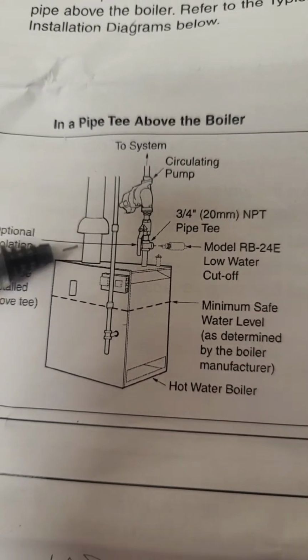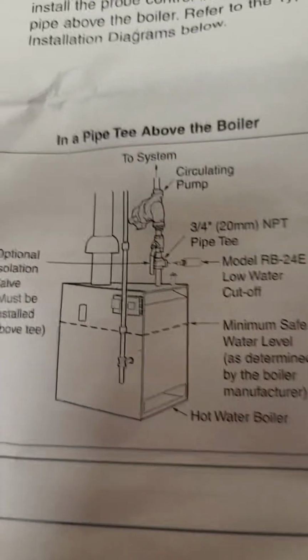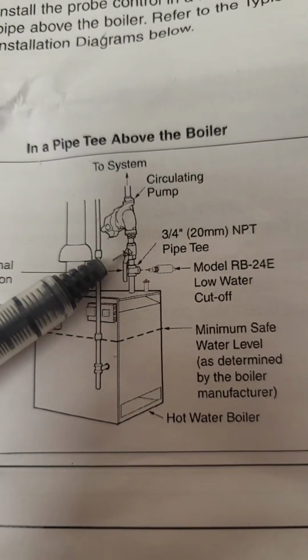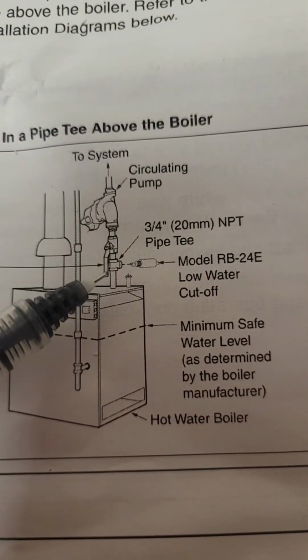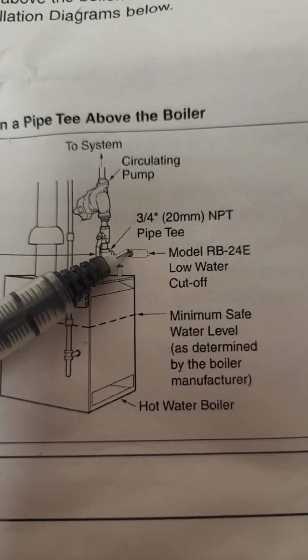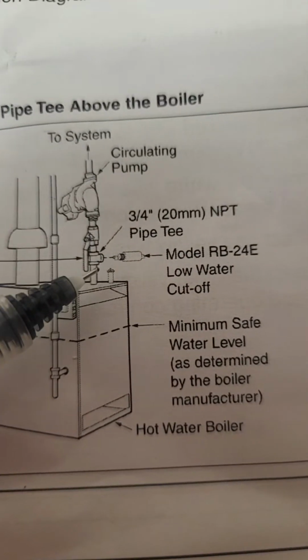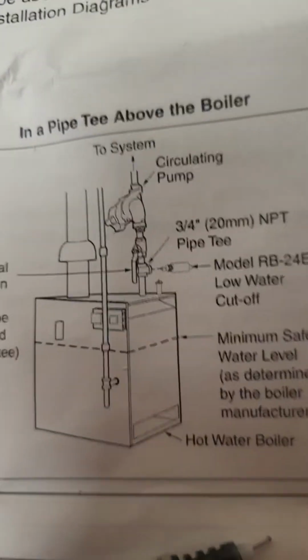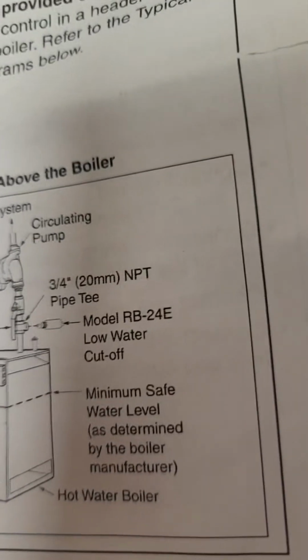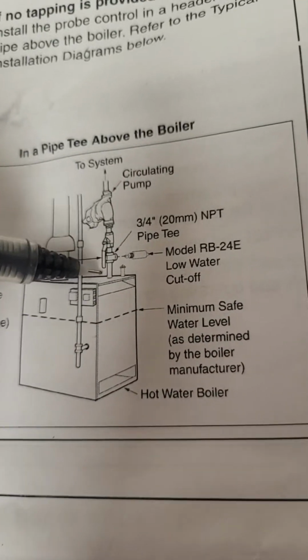The circulator pump could be on the supply or return, that doesn't matter. But if you're putting in the isolation T, this is going to help you valve off the T, and it's going to help you save some time whether you're having to replace this low water cutoff or not.